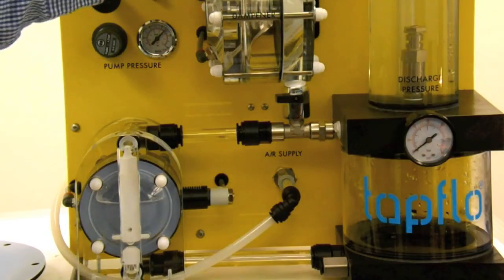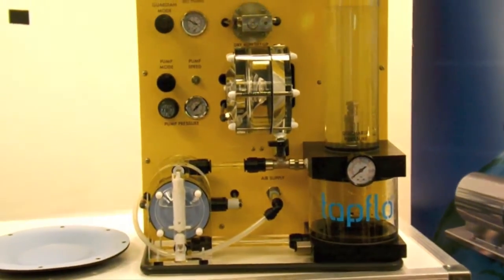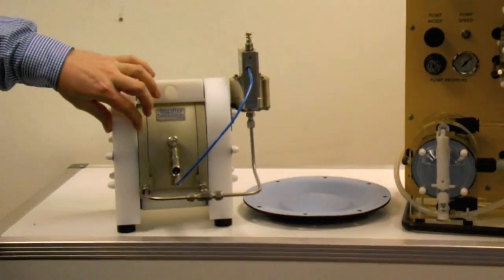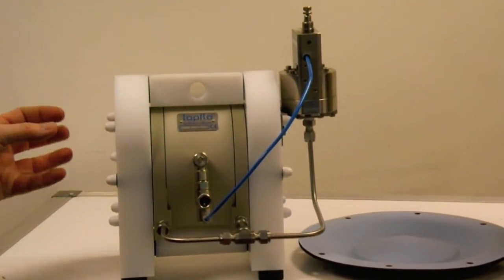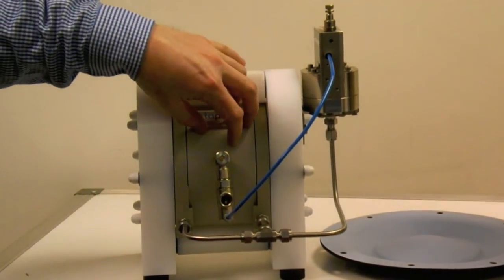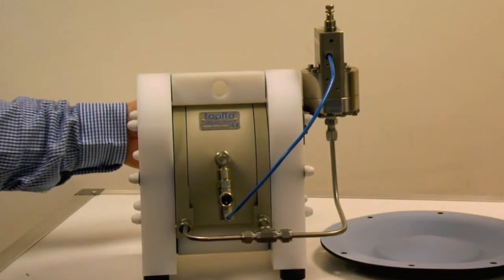Another very useful application for the guardian is on barrier pumps. Normally on your standard diaphragm pump you have two diaphragms, one on the left side and one on the right side. If either of those diaphragms fail product then gets pushed from the liquid side through the failed diaphragm onto the air side of the pump and gets exhausted as a spray or a leak out of the exhaust muffler.